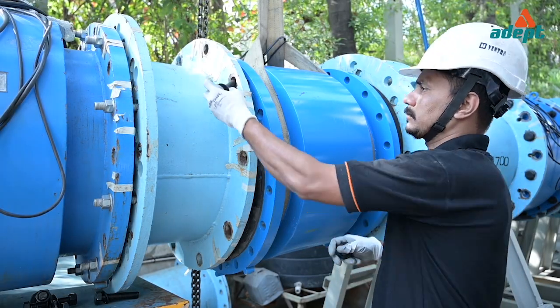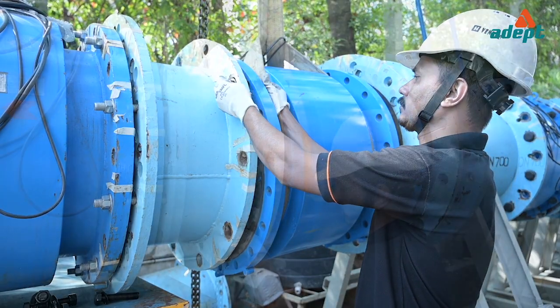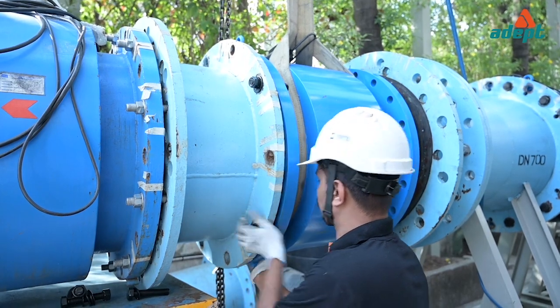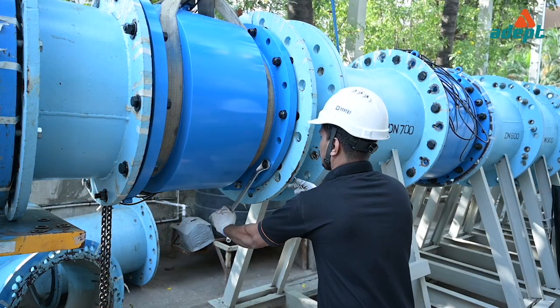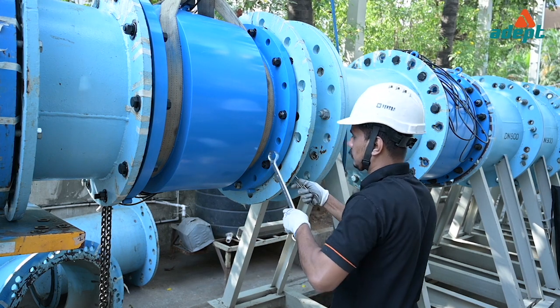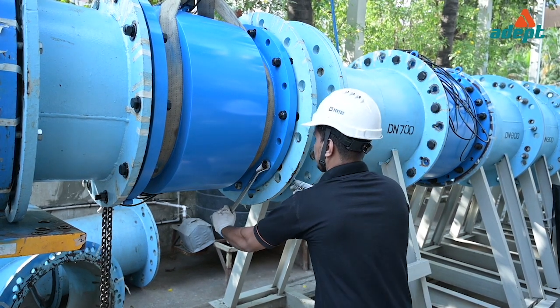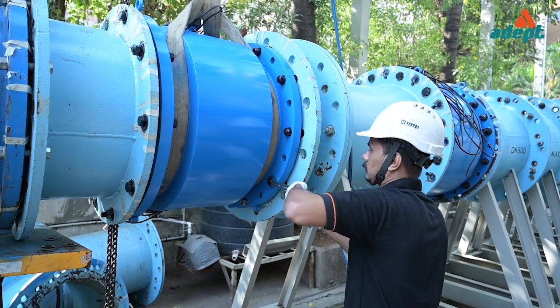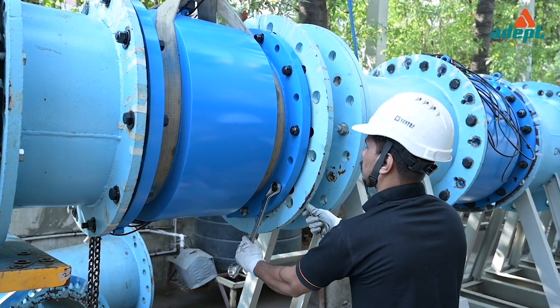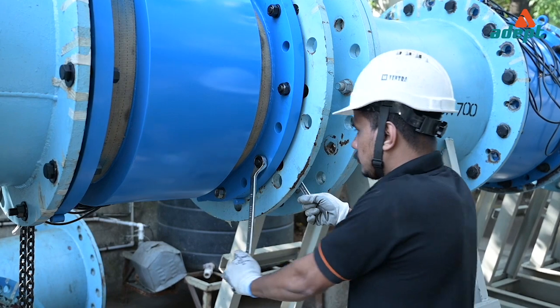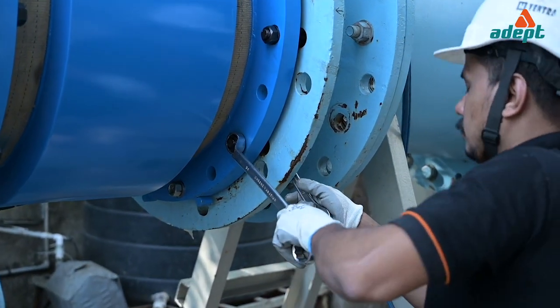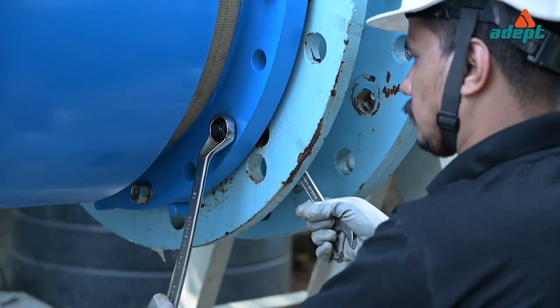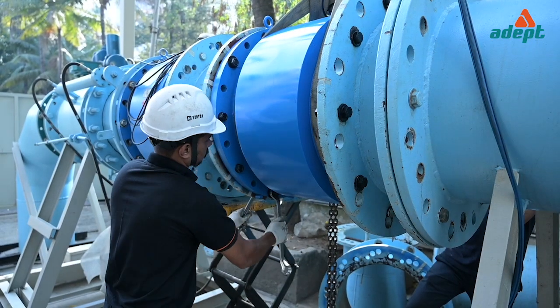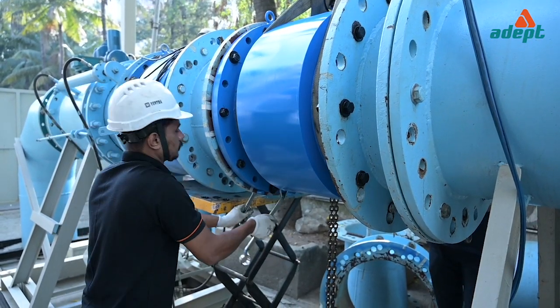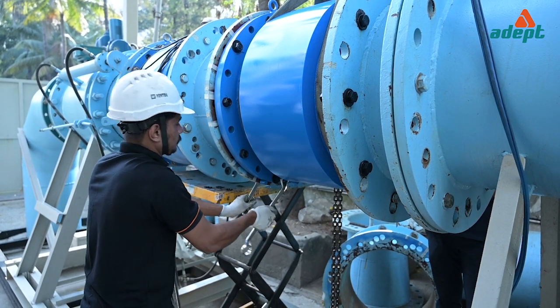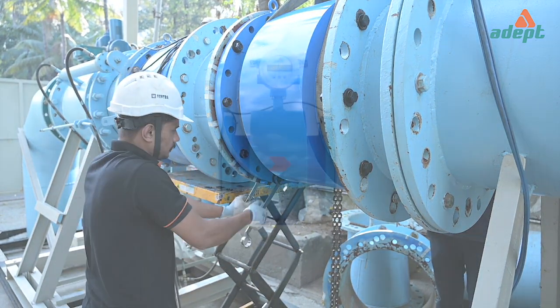Tightening of flange bolts. Apply a thin layer of fresh industrial grease to the threads of the bolt prior to tightening. Tighten all the mounting bolts uniformly without under or over tightening of any bolts. Tighten the bolts in a cross sequence as per the flange's size. Use an appropriate spanner or torque wrench. During the first pass, tighten to approximately 50%. During the second pass, approximately 80%, and only during the third pass to 100% of the maximum torque.